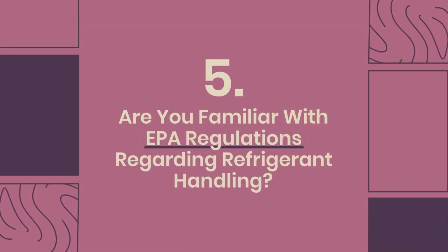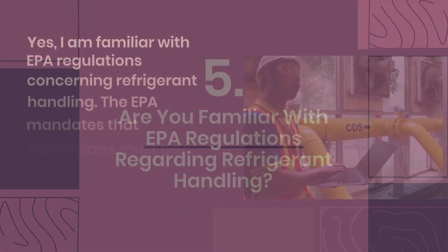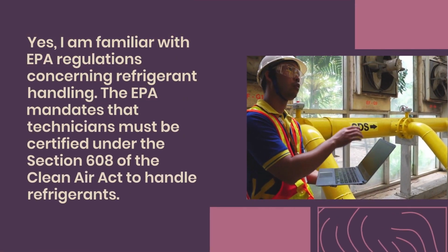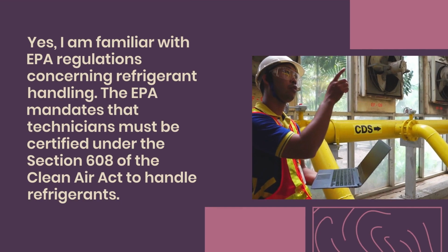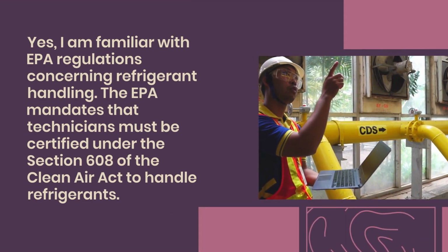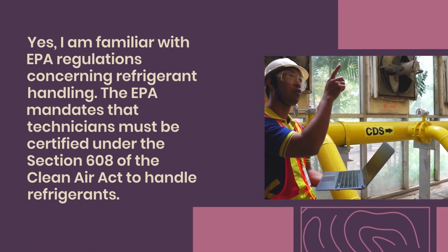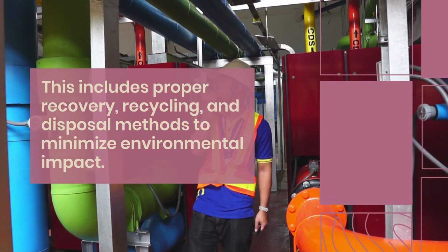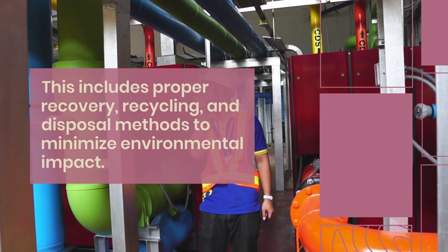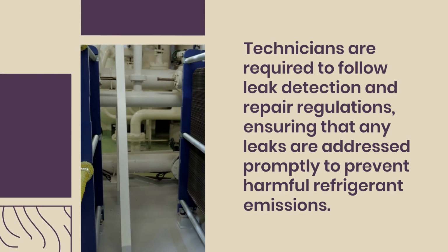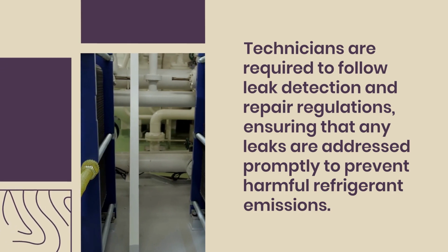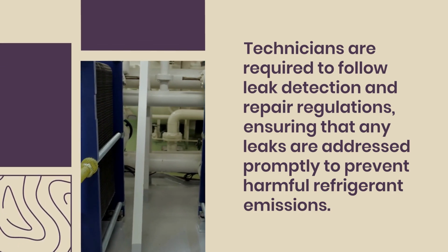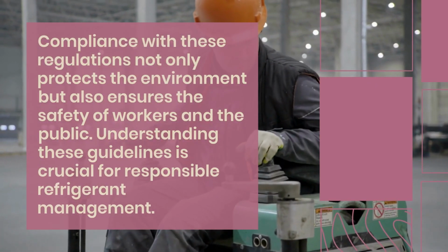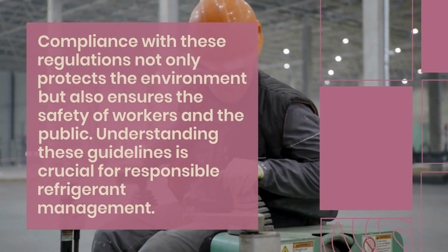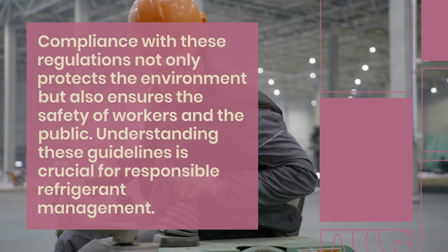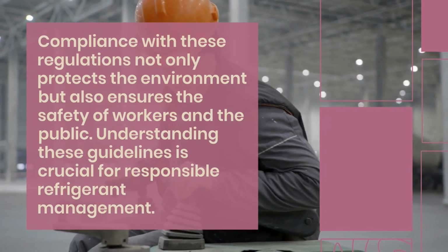5. Are you familiar with EPA regulations regarding refrigerant handling? Yes, I am familiar with EPA regulations concerning refrigerant handling. The EPA mandates that technicians must be certified under Section 608 of the Clean Air Act to handle refrigerants. This includes proper recovery, recycling, and disposal methods to minimize environmental impact. Technicians are required to follow leak detection and repair regulations, ensuring that any leaks are addressed promptly to prevent harmful refrigerant emissions. Compliance with these regulations not only protects the environment but also ensures the safety of workers and the public. Understanding these guidelines is crucial for responsible refrigerant management.